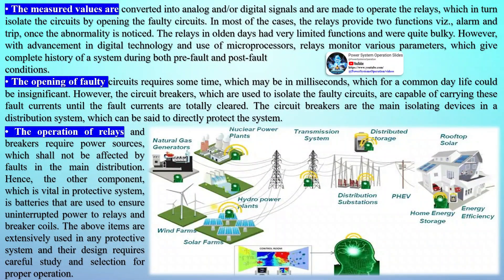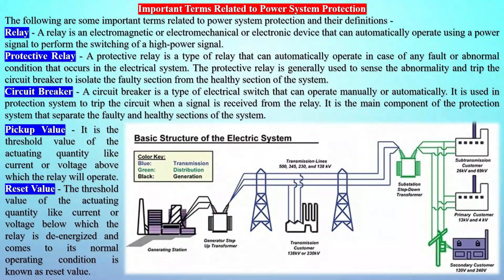Accurate protection cannot be achieved without properly measuring the normal and abnormal conditions of a system. In electrical systems, voltage and current measurements give feedback on whether a system is healthy or not. Voltage transformers and current transformers measure these basic parameters and are capable of providing accurate measurement during fault conditions without failure. The measured values are converted into analog and/or digital signals and are made to operate the relays, which in turn isolate the circuits by opening the faulty circuits. In most cases, the relays provide two functions: alarm and trip, once the abnormality is noticed.